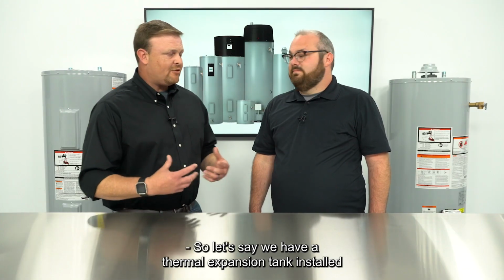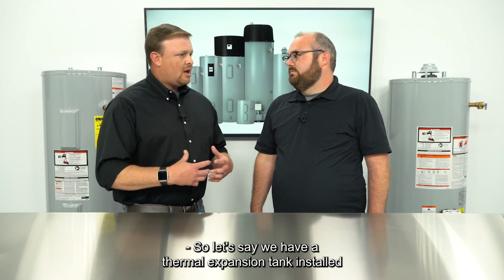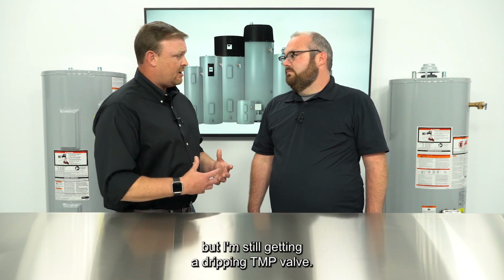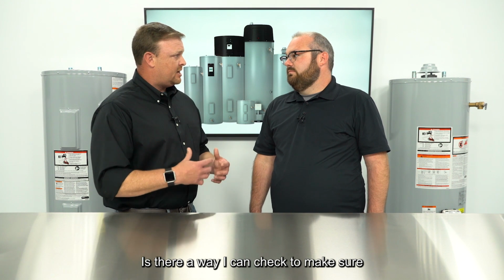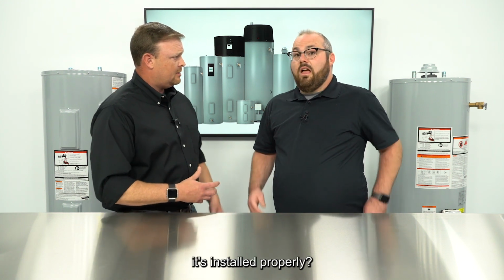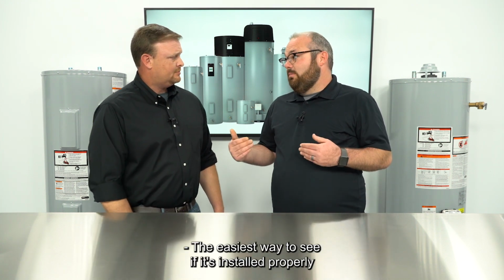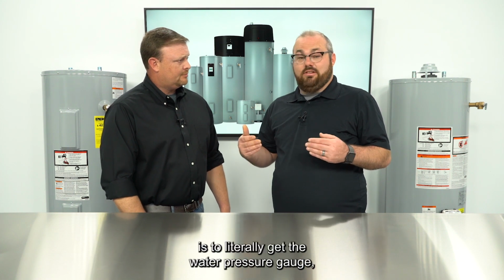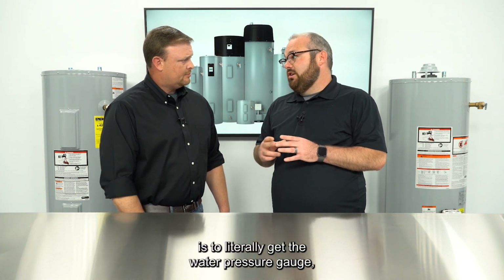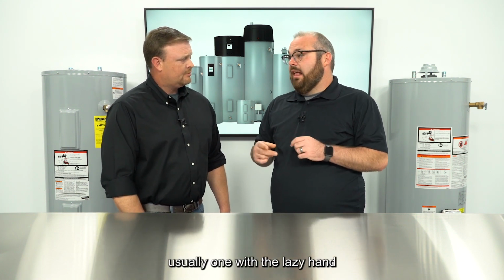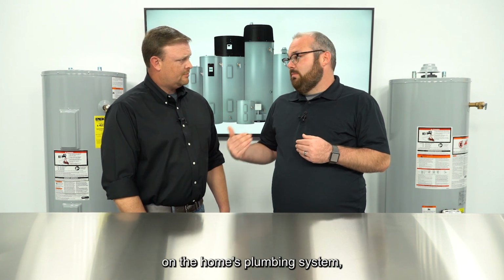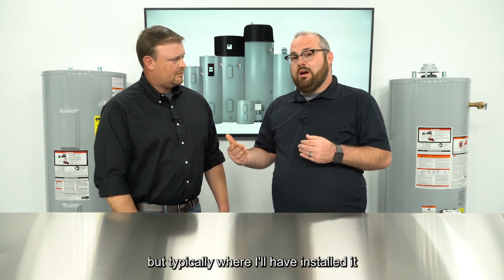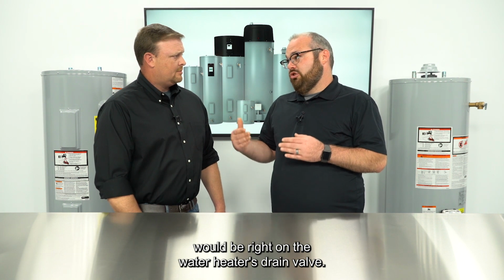So let's say we have a thermal expansion tank installed, but I'm still getting a dripping T&P valve. Is there a way I can check to make sure it's installed properly? The easiest way to see if it's installed properly or if it's functioning is to get a water pressure gauge, usually one with a lazy hand. You can install it anywhere on the home's plumbing system, but typically I would install it right on the water heater's drain valve.